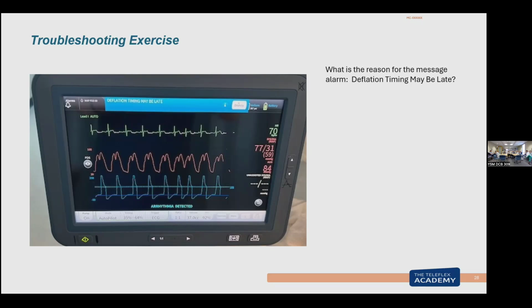Well, that was an occasional one. If it was frequent, with a short cycle, and I'm getting late deflation alarms, then I may have to look at whether I need to adjust my timing. I may have to go to operator mode and change it, because late deflation can be bad for patients, not always. So I can assess that.